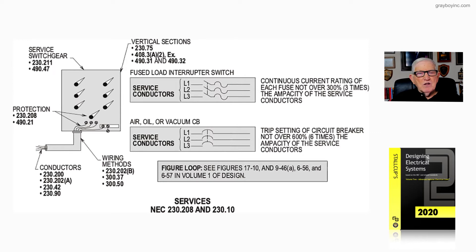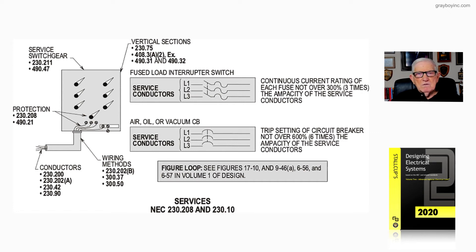For your conductors, we go to 230.200, 230.202A, 230.42, and 230.90 for ampacity. Go to the new Article 311 and select a table based on conductors in conduit or cables — whether in conduit in the ground, above ground, and so forth. To select your circuit breakers, fuses, switchgear, switchboard, or panelboard, you have to go to Article 490, which we have referenced for you there.